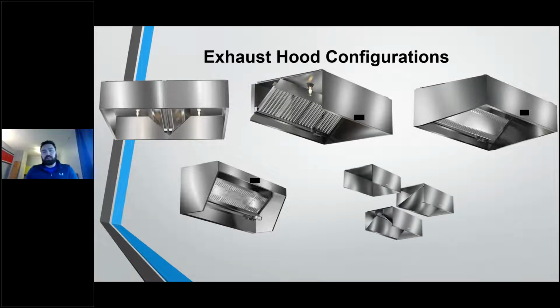The final hood configuration that you're going to see in the market is a Type 2 style hood. So whether that's a heat-only hood or some combination of condensate baffles in a Type 2 hood, this is going to be the configuration of your Type 2 hoods. The condensate baffles would be used over a condensate application, such as a dishwasher, and that's going to be used to knock the condensate out of the air. Typically, you're going to have some sort of a perimeter gutter with these as well. That's going to go down to the drain line. So these are the hoods that we're seeing predominantly used in the market.